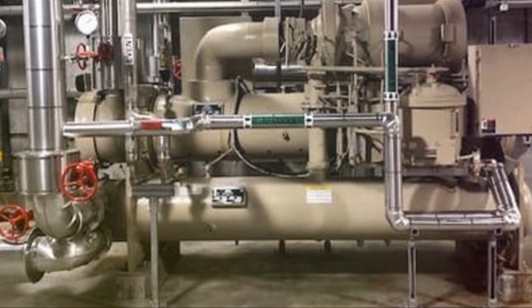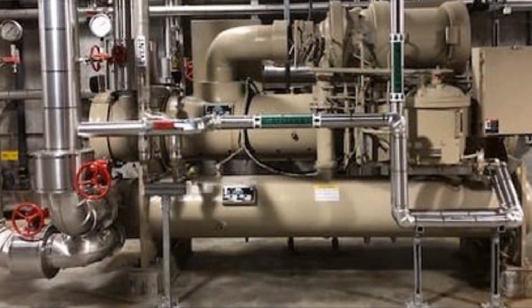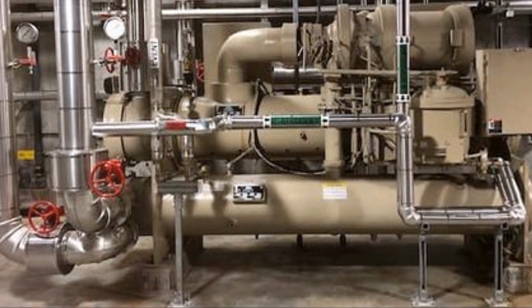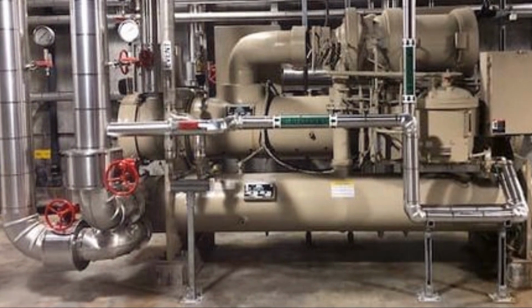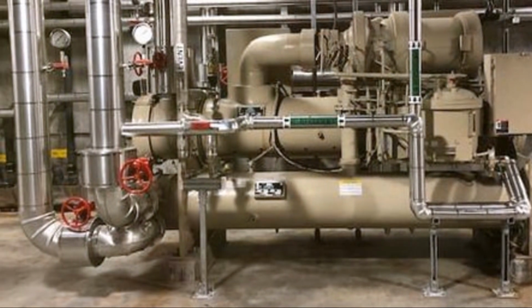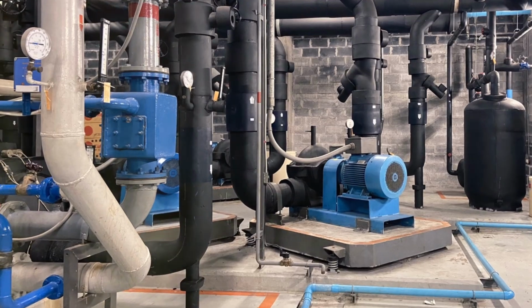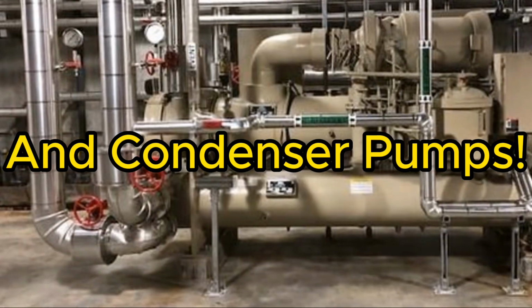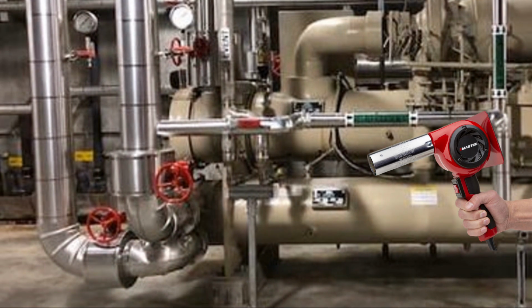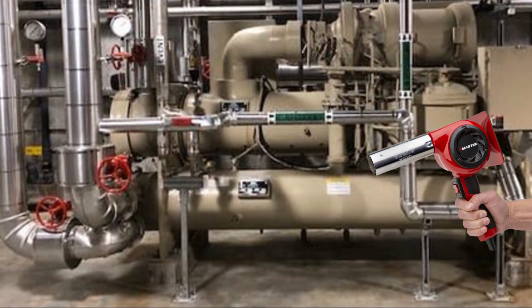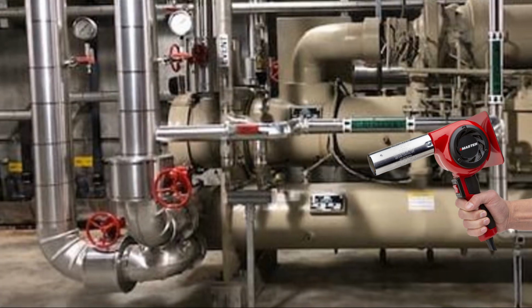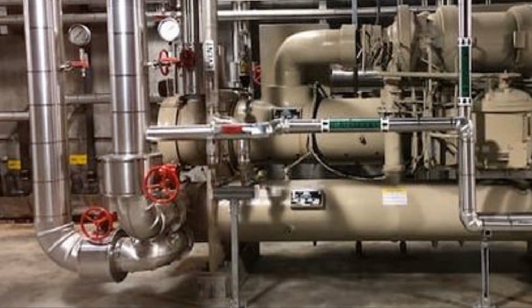After that, you will look for cold spots on the machine, and use your pressure gauge on various ports to make sure that there is no liquid refrigerant trapped in the machine. Then either take a break or continue to run the evaporator pumps, and maybe even warm the bottom of the condenser and other cool points with a heat gun. You'll do this until you are 100% certain that you have all of the liquid refrigerant out of the machine. All of this will be done with the recovery machine off.